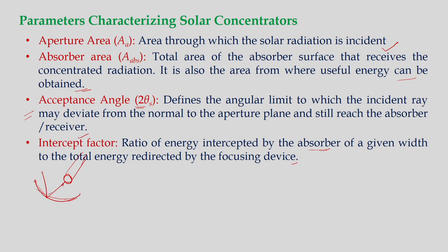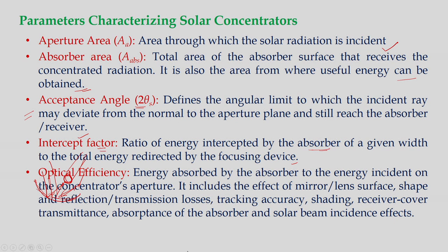Some radiation may not strike the absorber — it may go off and not reach it, so the intercept factor needs to be considered. We always look for unity but will not always achieve it. Optical efficiency defines the ratio of energy absorbed by the absorber to the energy incident on the concentrator's aperture. It includes the effect of mirror or lens surface shape and reflection/transmission losses, tracking accuracy, shading, receiver cover transmittance, absorptance of the absorber, and solar beam incidence effects.